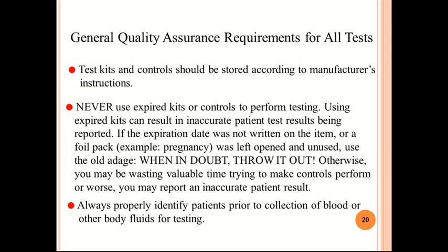Test kits and controls should be stored according to manufacturer's instructions. Never use expired kits or controls to perform testing. Using expired kits can result in inaccurate patient test results being reported. If the expiration date is not written on the item or the foil pack, for example a pregnancy test that was left open or unused, when in doubt, throw it out.